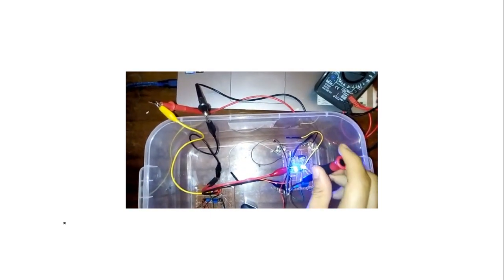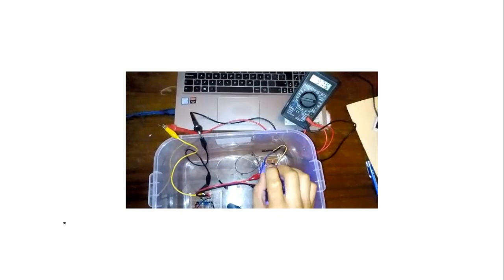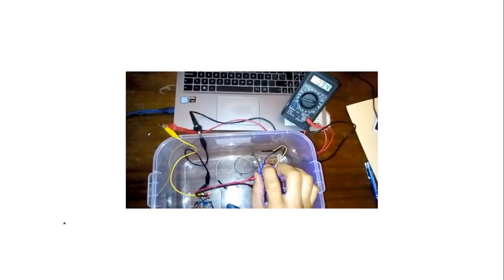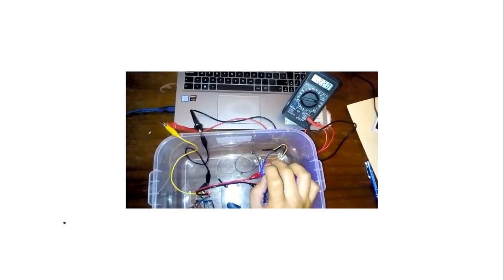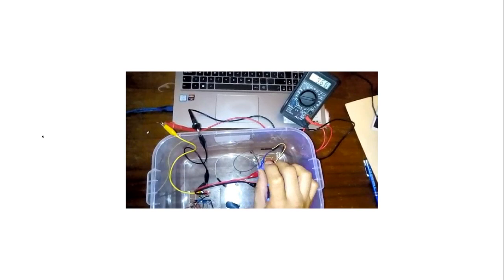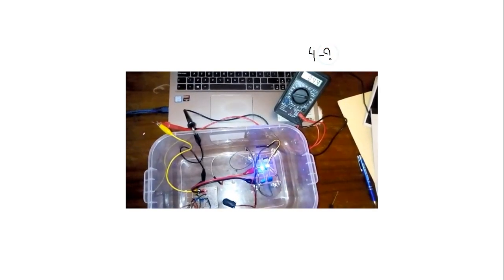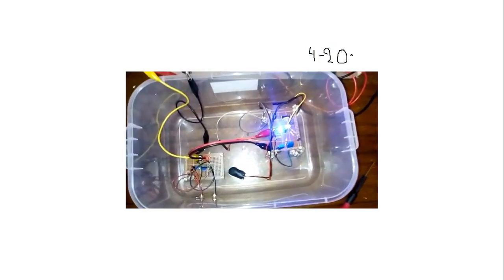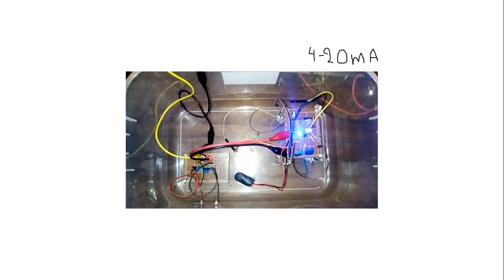Here I am adjusting the potentiometer. As you see, here we have 10 milliamps, 11 milliamps, 12 milliamps, the opposite, 10 milliamps. So this is from 4 to 20 milliamps. This is the circuit of 4 to 20 milliamps.